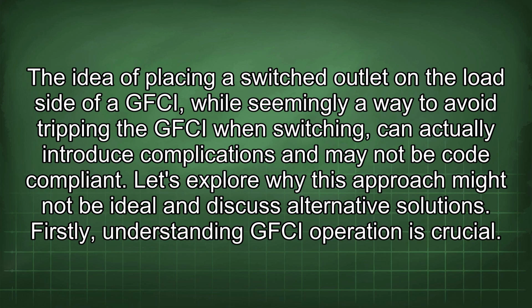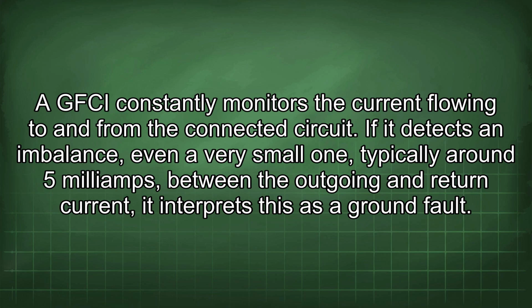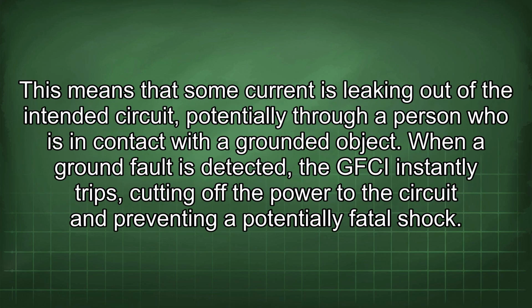Firstly, understanding GFCI operation is crucial. A GFCI constantly monitors the current flowing to and from the connected circuit. If it detects an imbalance, even a very small one, typically around 5 mA between the outgoing and return current, it interprets this as a ground fault. This means that some current is leaking out of the intended circuit, potentially through a person who is in contact with a grounded object. When a ground fault is detected, the GFCI instantly trips, cutting off the power to the circuit and preventing a potentially fatal shock.